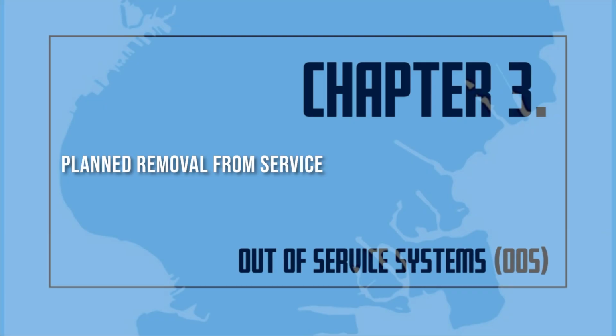The impairment coordinator shall authorize and personally supervise the placing of the fire protection system out of service. Before authorizing the placing of the fire protection system out of service, the impairment coordinator shall notify the certificate of fitness holder responsible for supervising the maintenance of the standpipe system, sprinkler system, or fire alarm system. Determine the extent and expected duration of the out-of-service condition. Inspect the areas or buildings involved and assess the increased risks. Make appropriate recommendations to the owner.